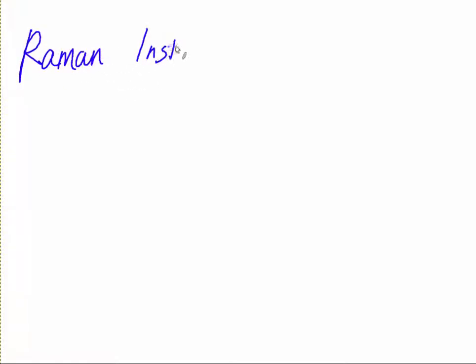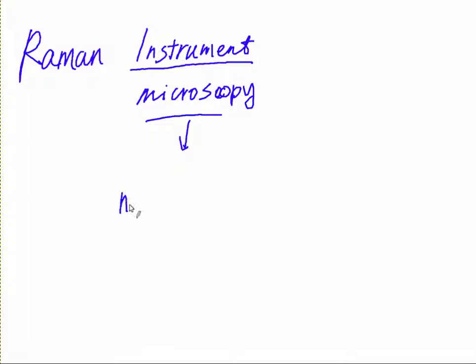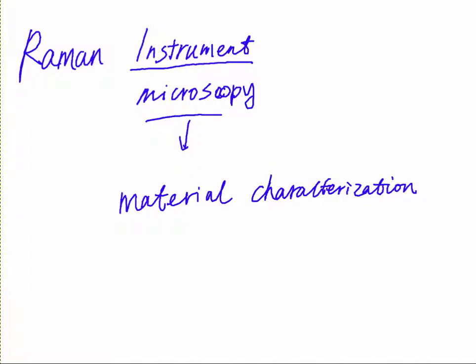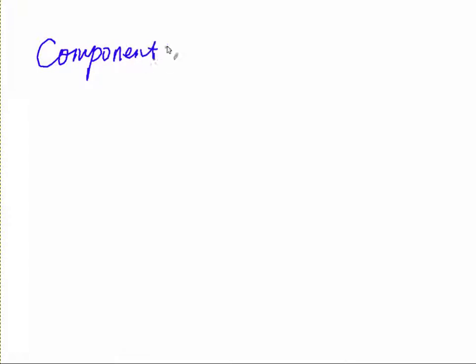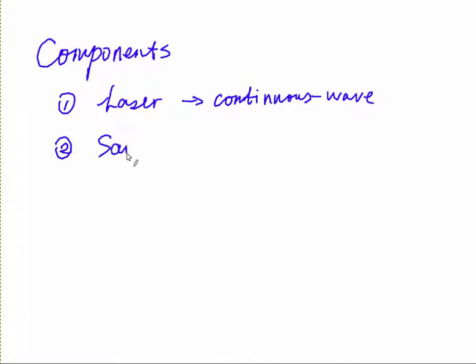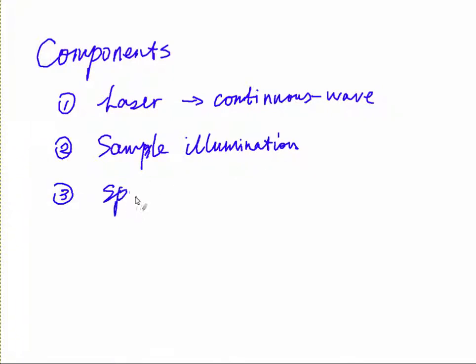Now we introduce some things about the Raman instrument. We mostly talk about Raman spectroscopy, which is usually used for materials characterization. In a Raman microscope, the components typically include a laser source — a continuous wave laser — as well as a sample illumination system and collection system. The third component is a spectral analyzer, and the fourth is a detector to detect the Raman signal.